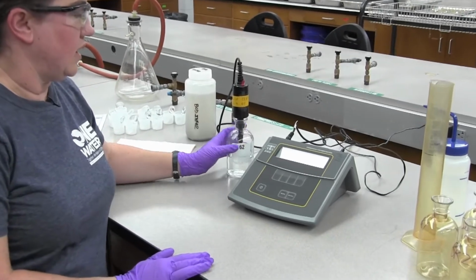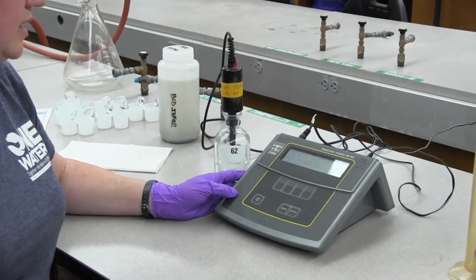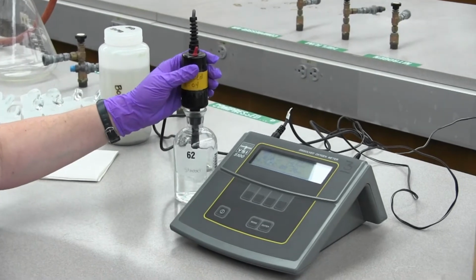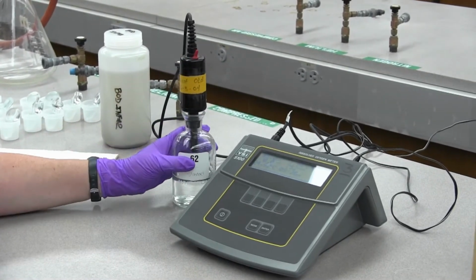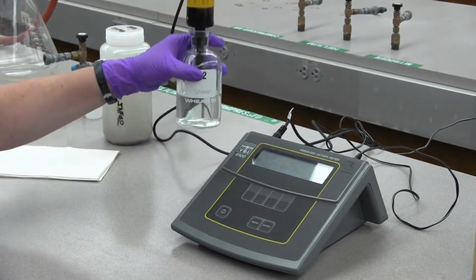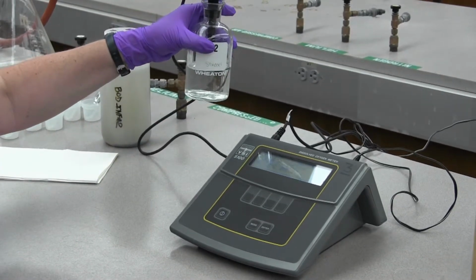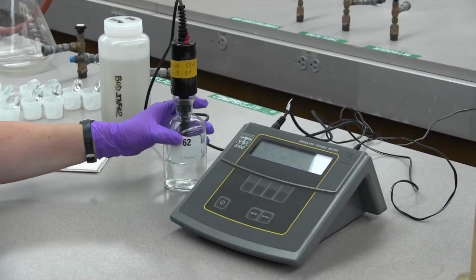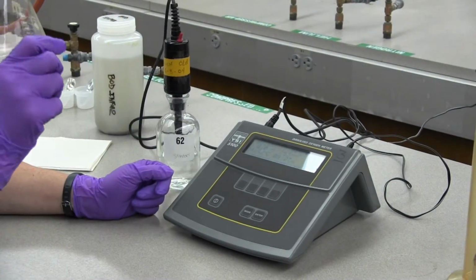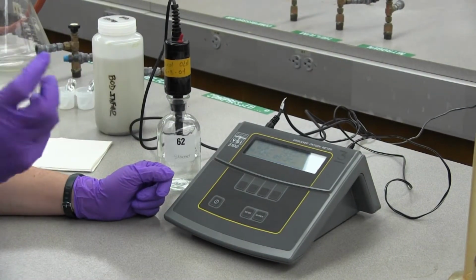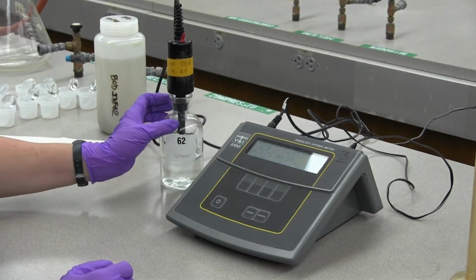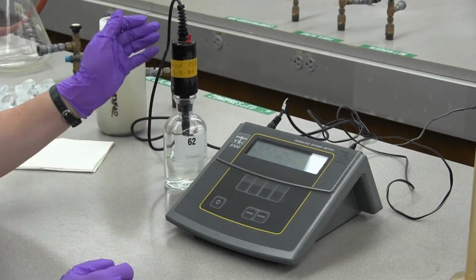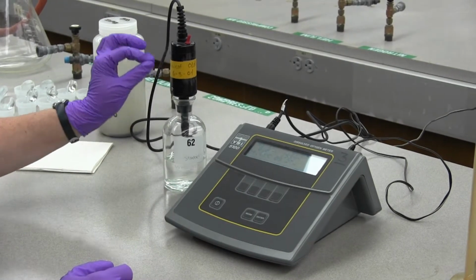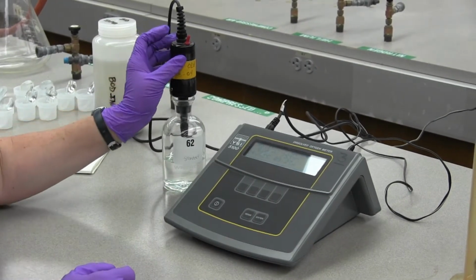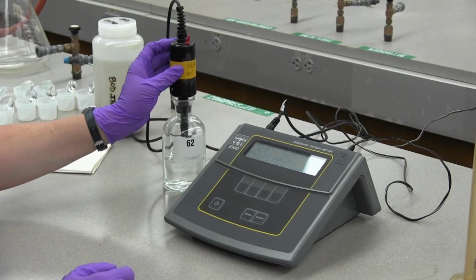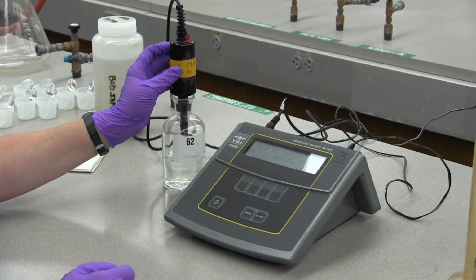First of all, we have a YSI meter here. We have our probe hooked up to it. The first thing that you want to do is put just a small amount of water in there, maybe around an inch of water, and you want to stopper the bottle, shake it vigorously for about 30 seconds, and also rinse off the probe and the membrane, and then put it in the bottle for 10 minutes. That way it'll stabilize and you're ready to calibrate the meter.